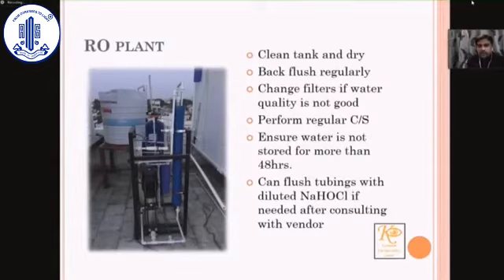If you're planning to shut down, empty the tank, clean it with sodium hypochlorite, dry it and seal it, ready to be used again. Before decommissioning the plant, make sure you perform the back flush function, which is already present in most RO plants, and cut off the water supply. During the recommissioning phase, again clean the water tank, check the filters with the help of your vendor, and perform a water quality test as per ISO standards, including culture sensitivity. Discard the first tank or filter of water and start using after that.